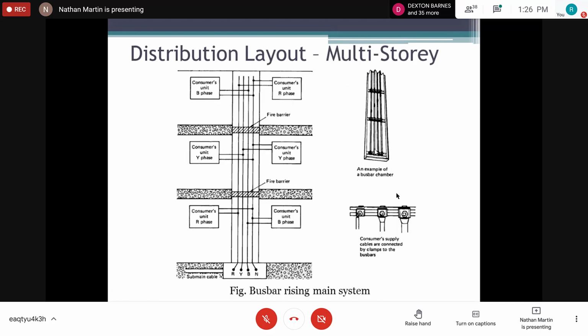For a multi-story layout, now we're talking about apartment complexes that are about 3 or 4 stories. We're talking about our riser mains, right, our bus bar risers that will run alongside. So when you talk about this type of installation, a lot of the time the utility room will be in the same position throughout, right? So it's just a matter of your utility room being above the lower utility room for easier access, right? So when it goes to the other floor, it's just a matter of taking it to your different consumer units, right? Which is basically your distribution panel box.